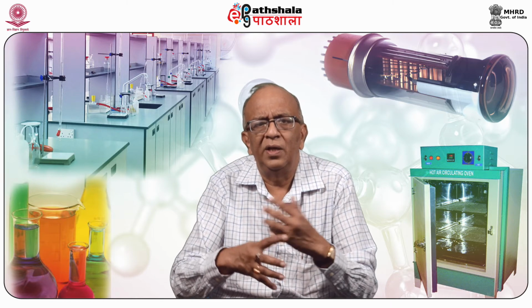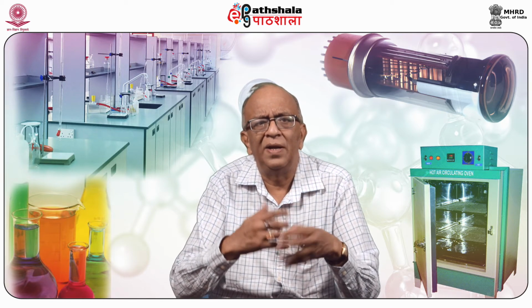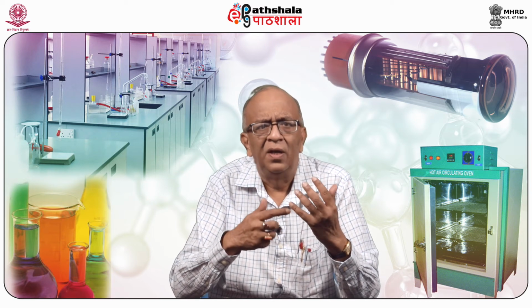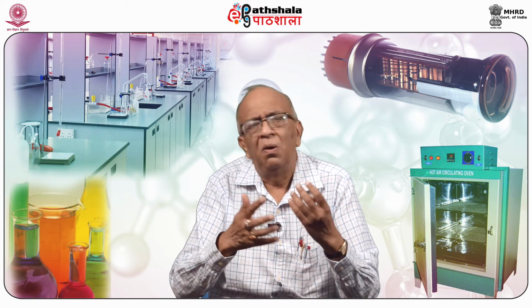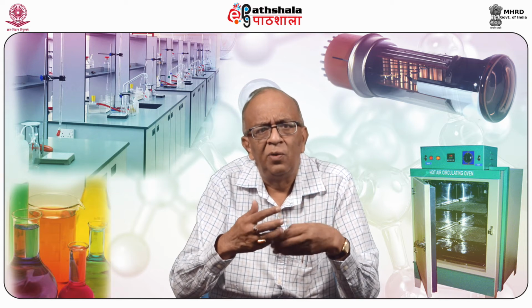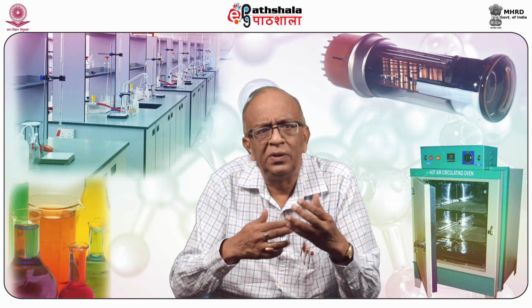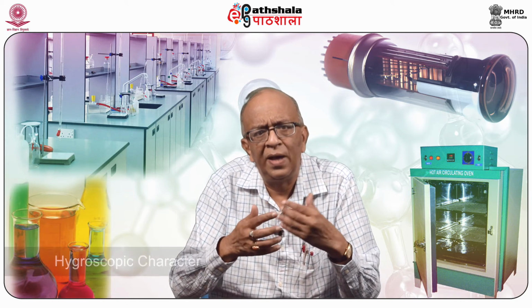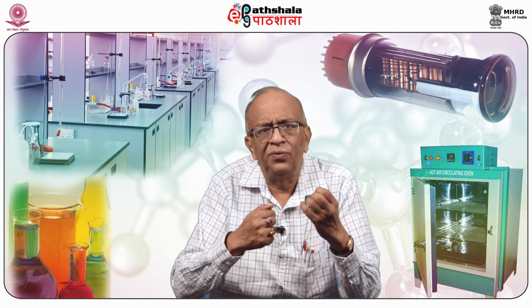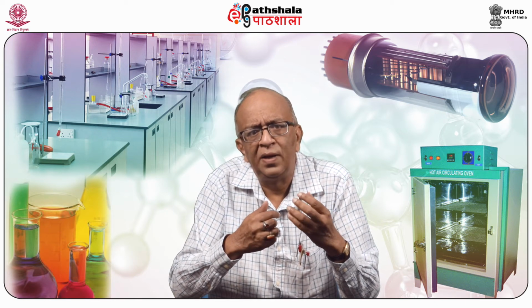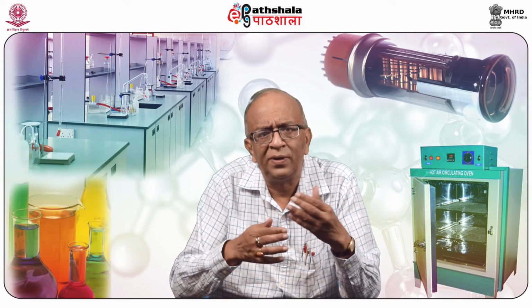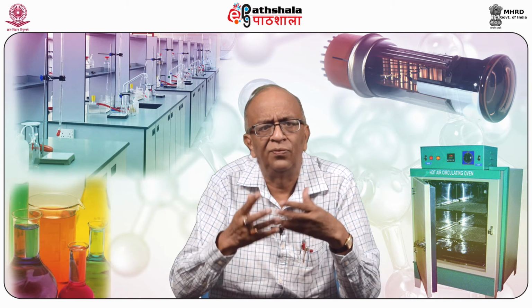Another important property of ion exchanger, which may be cation exchanger or anion exchanger, is the swelling. That is, on taking the molecules of water, it swells. The high proportion of polar groups within the resin gives a hygroscopic character. In a sulfonate resin, one can consider that the SO3 and H+ ions dissolve in the adsorbed water, yielding a solution of high concentration.